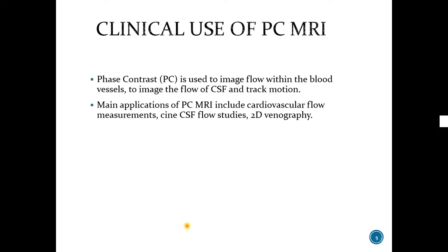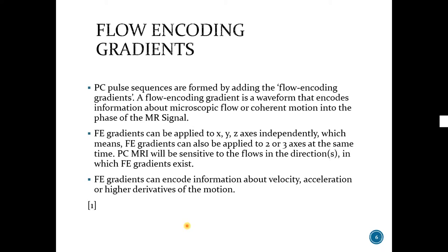Flow encoding gradients are very crucial in PC MRA because PC pulse sequences are formed by adding the flow encoding gradients. These gradients encode the information about flow or motion into the phase. Flow encoding gradients can be applied in x, y, or z directions independently, so they can be applied in 2 or 3 directions. In that case, PC MRA will be sensitive to the flows in the directions in which flow encoding gradients are applied. Flow encoding gradients can encode information about velocity, acceleration, or higher derivatives of the motion.